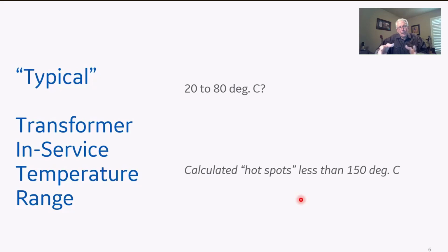So keeping the temperature right on our winding paper is rather critical, because think about what you can repair in a transformer versus what you can't. If you begin to develop thermal in the transformer and the paper's okay, you know it's outside the winding, and you can likely repair that if you catch it before it flashes over and destroys the transformer. In some cases, you may flash over and still be able to go in and repair it. As hot metal gas builds in the transformer, if it's not happening in the winding, there's a very good chance you'll be able to fix the problem if you get in there soon enough. It's a matter of knowing when to go in so it becomes visible.